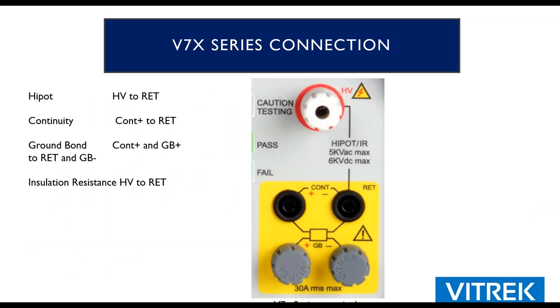And then this is basically the way that you connect them on the front panel. This is a common question: okay, I have my Hipot tester, now how do I connect it to my DUT? And we've shown it here on this graph. So you can see a Hipot or IR test is always going to be from the high voltage to the return terminal. Continuity is going to be from the return terminal to the continuity source terminal, and that's always going to be a 2-wire measurement.